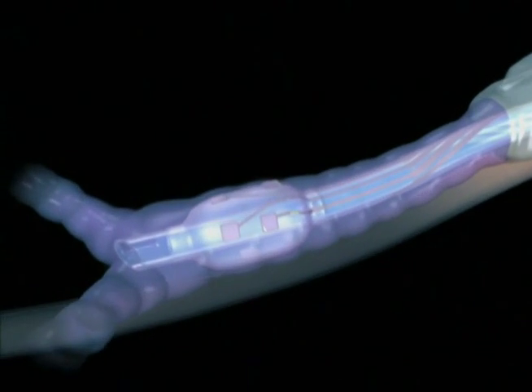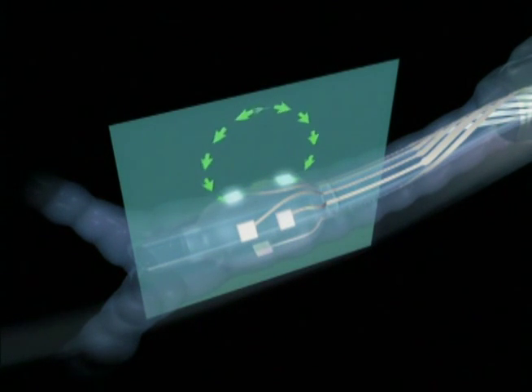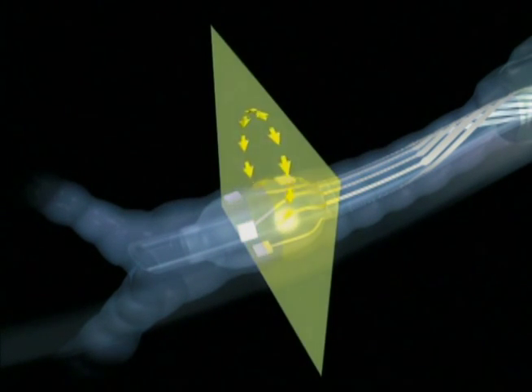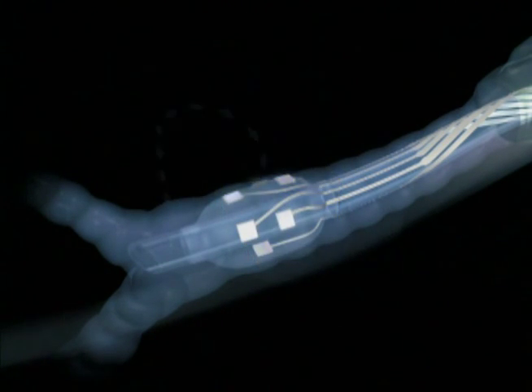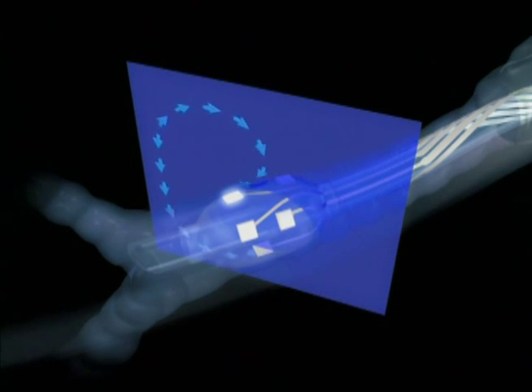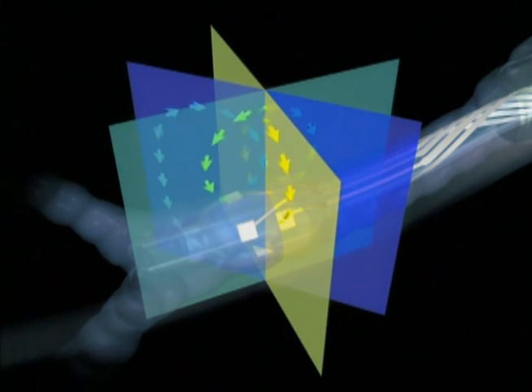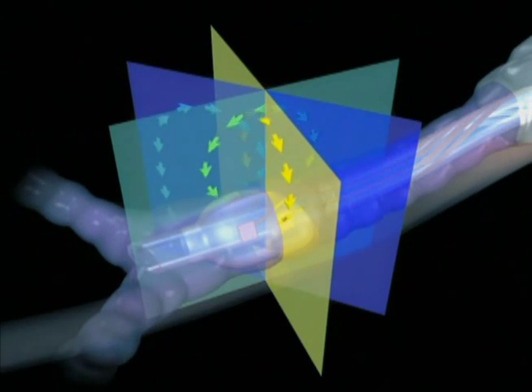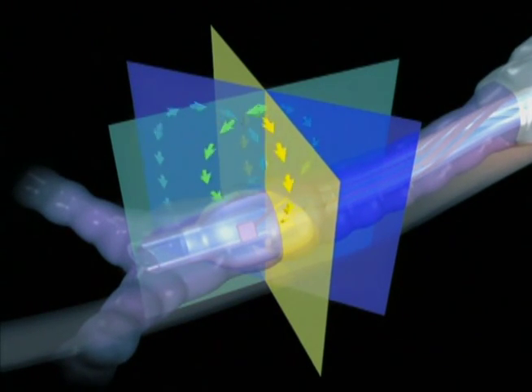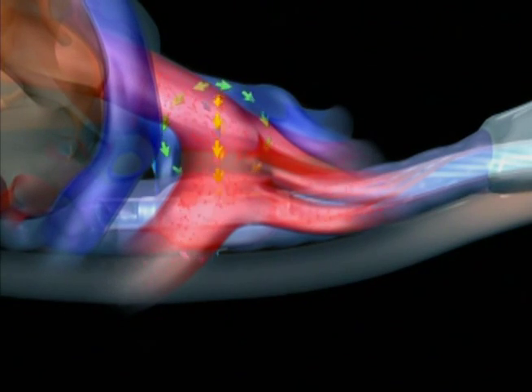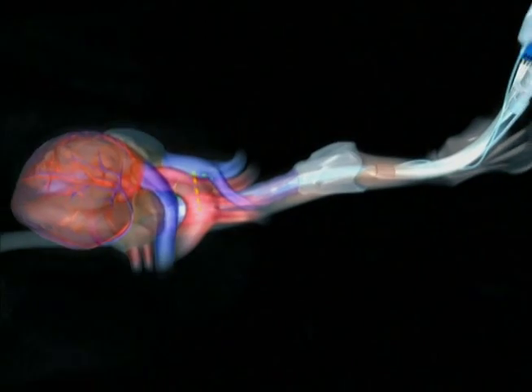3 orthogonal pairs of sensing electrodes on the cuff are used to measure the change in impedance caused by aortic blood flow. The orthogonal electrode pairs compensate for positional and anatomical differences between the cuff and the aorta. A total of 12 combinations of electrodes can be used for the impedance measurement of flow. If a signal is weak or lost on one channel, the ECOM software will search and select another electrode combination.